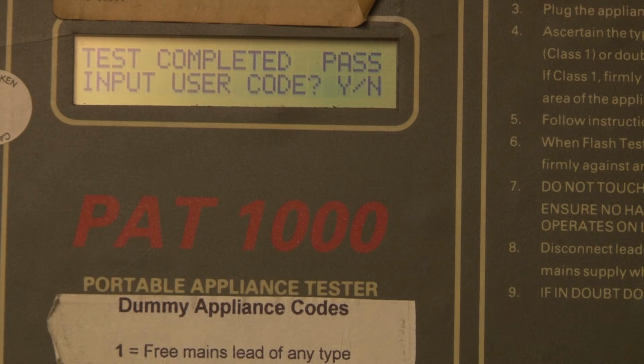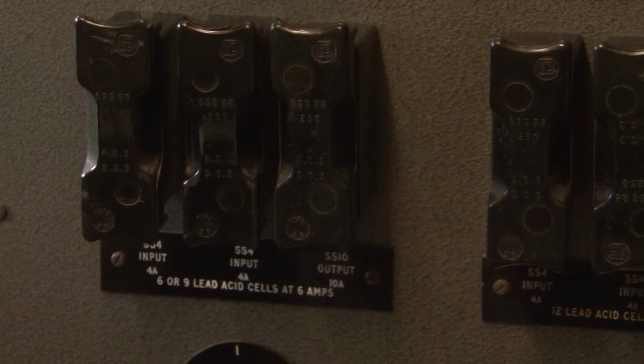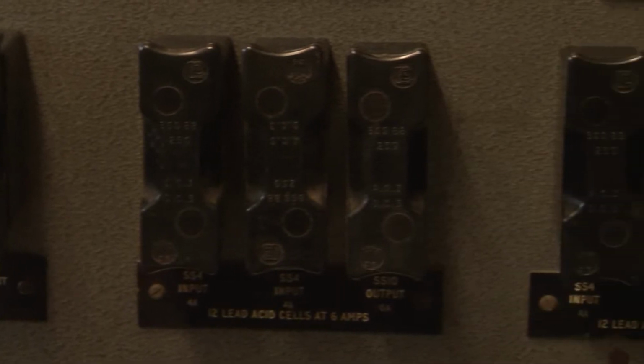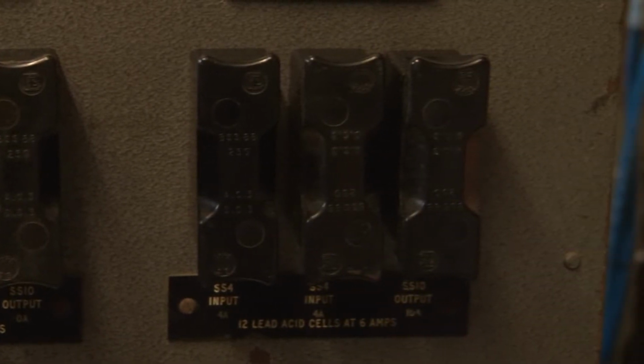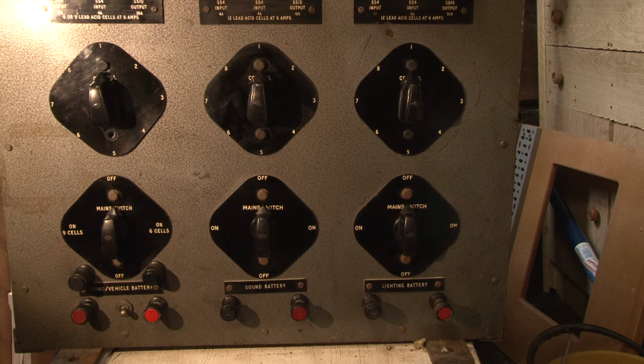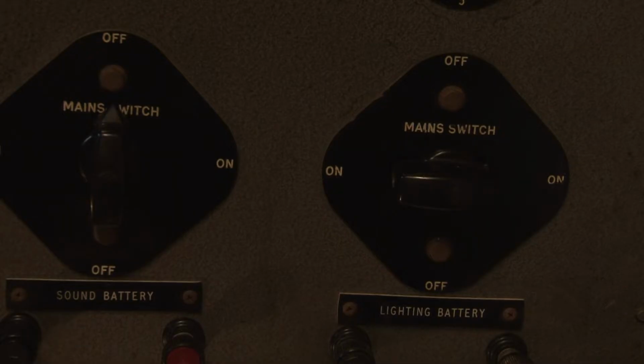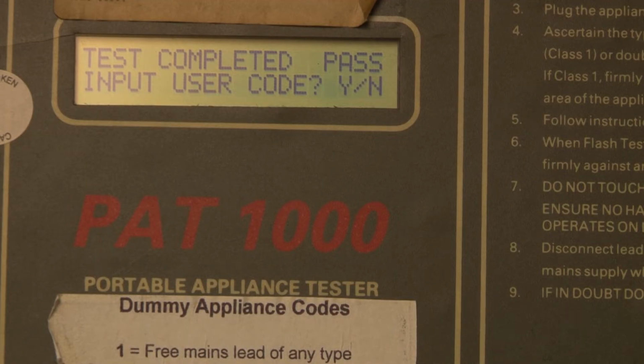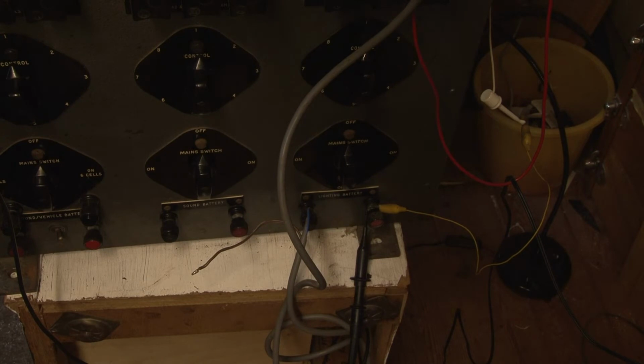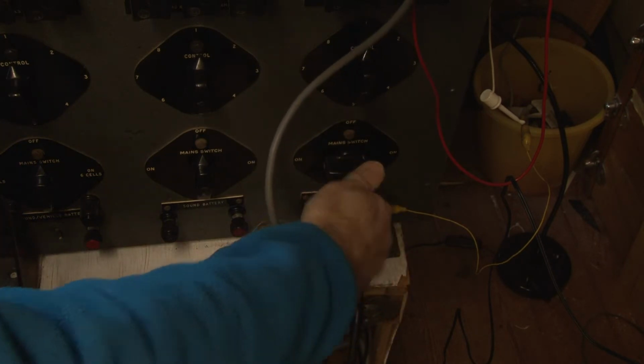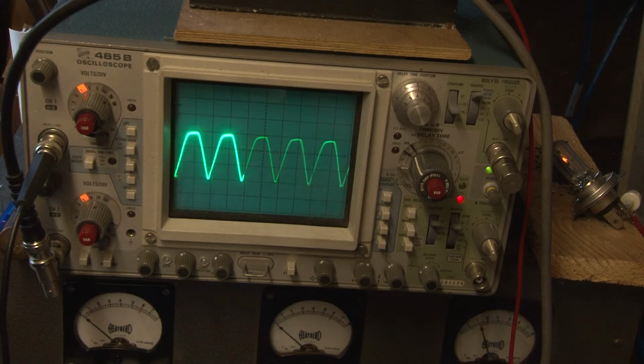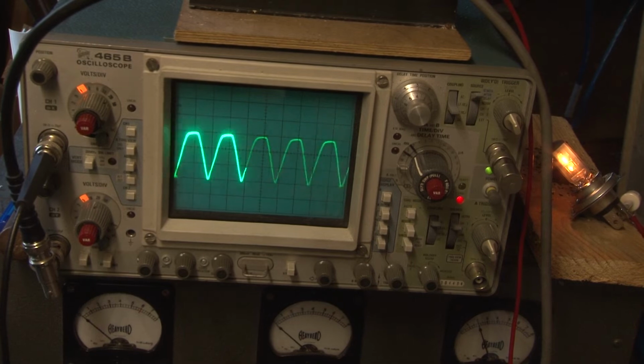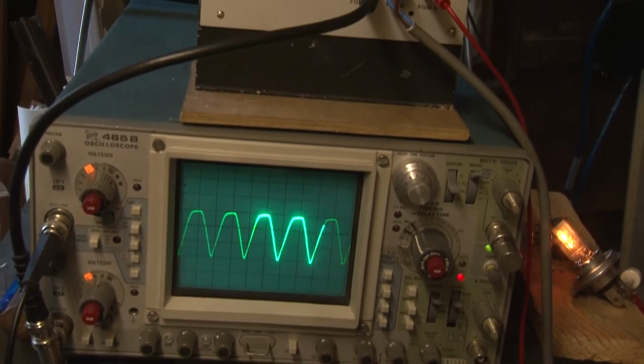So that's a good sign that this unit is at least electrically safe, and it's not going to give me a nasty belt or anything like that just by its general operation. Obviously I'm not going to go sticking my hands inside it, as there's a lot of exposed live terminals. I think now we can proceed to a functional test. So we'll switch on the lighting battery charger first and test that. And we'll just explain the dummy load that we've got connected across the system at the moment.